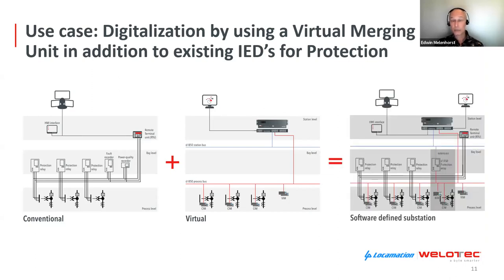The combination of existing secondary equipment with the state-of-the-art VMU platform will provide immediately accurate process information to new IEC 61850 IEDs, and future extensions of the substation become much easier. Even extending the substation with additional bays and IEC 61850 based IEDs will be less time consuming. The infrastructure is already present, working in parallel with the existing conventional relays.